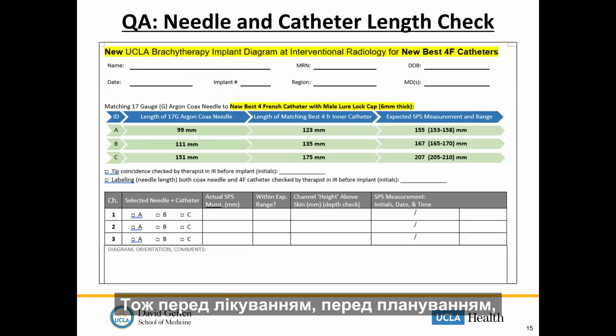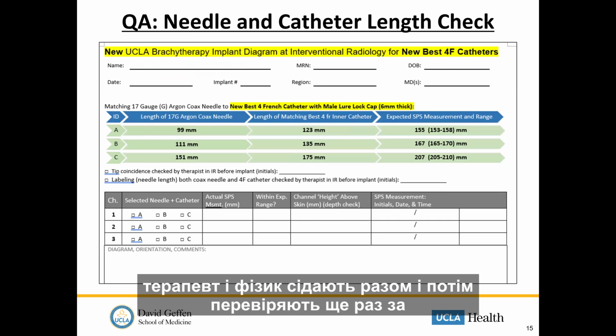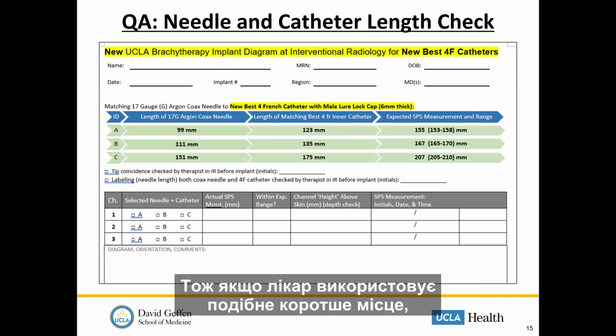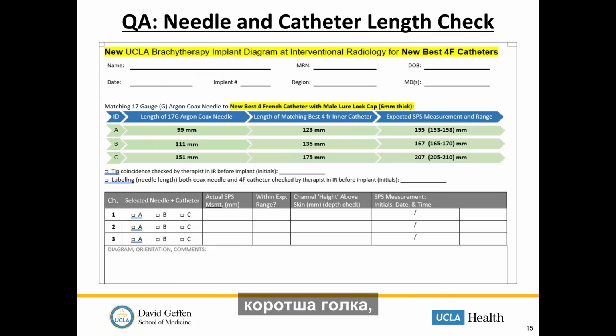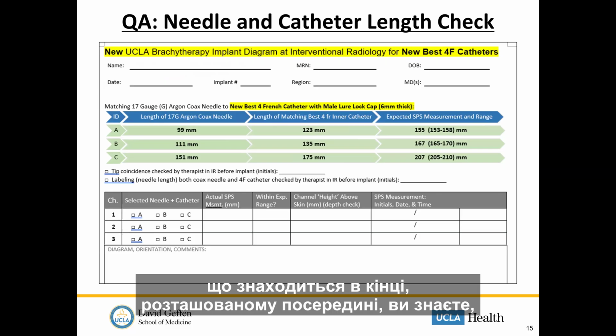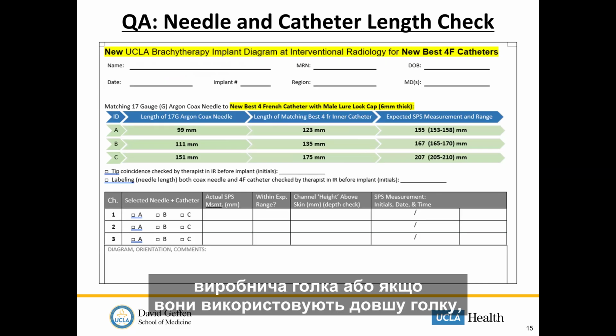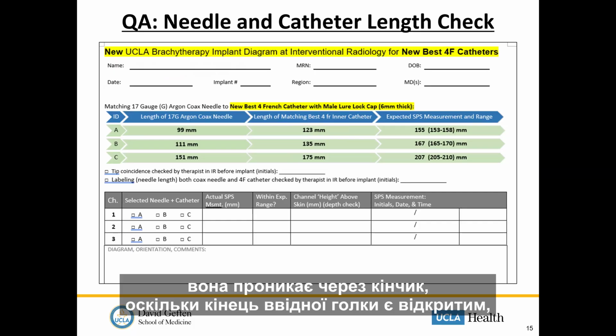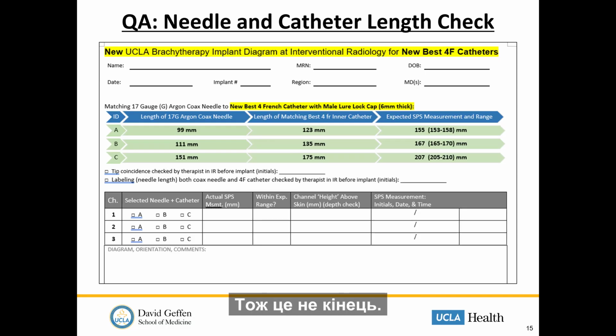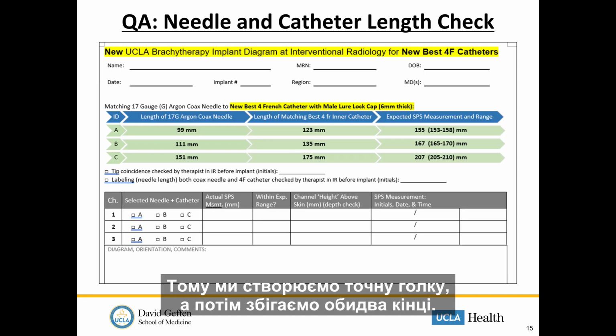So before the planning and the treatment, the therapist and physicist measure together and double check with this reference length. If the physician places a shorter needle, the tip end is located in the middle of the coaxial needle, or if they use a longer needle, it penetrates through the tip end, because the introducing needle end is an open end so they can do the biopsy. So that's not a stop. So we create the exact needle and coincide both tip ends.